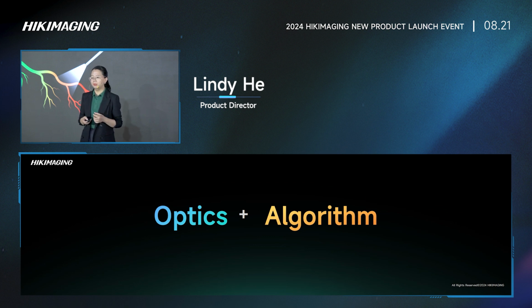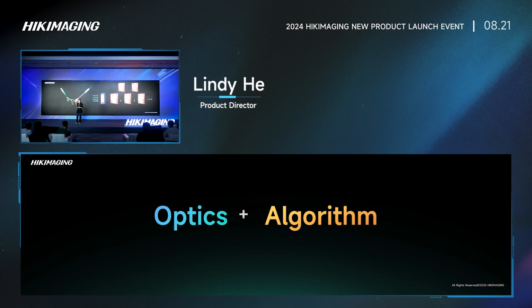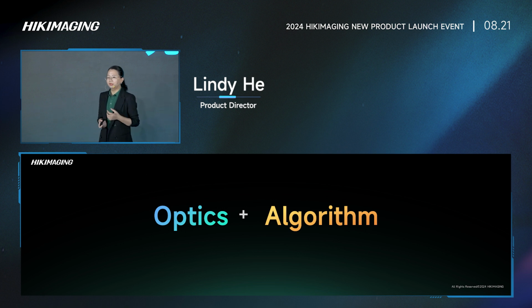The two sensors can only be used to collect white light and the fluorescent data. So when the fluorescent mode is on, the 3D endoscope needs to cooperate with the light source to collect the data. In one frame, it collects white light, and in the next frame it collects fluorescence. The light source flashing is then a stage of alternating white light and fluorescent excitation light. The collected data is then processed through an algorithm to create a 3D fluorescent image. This is how 3D fluorescent images are produced.